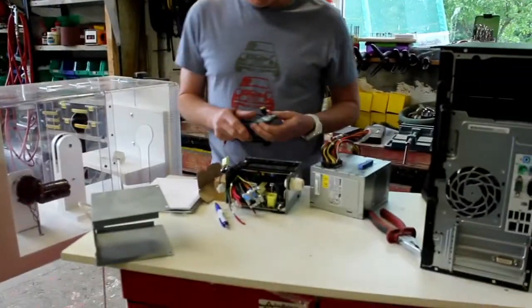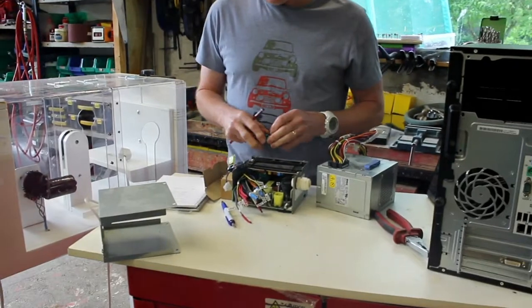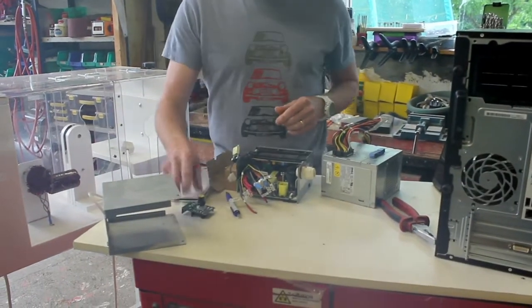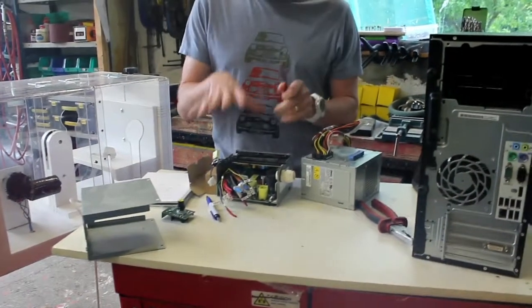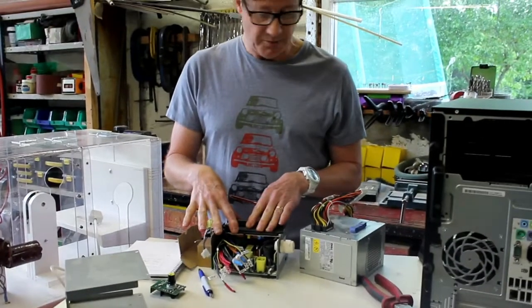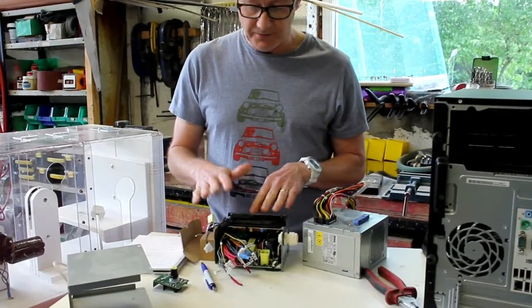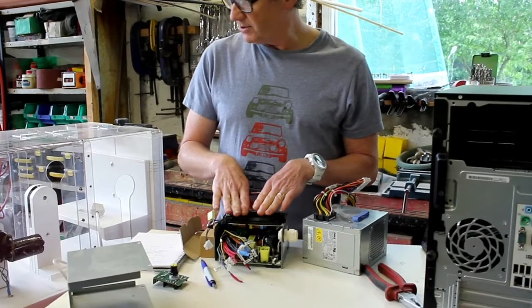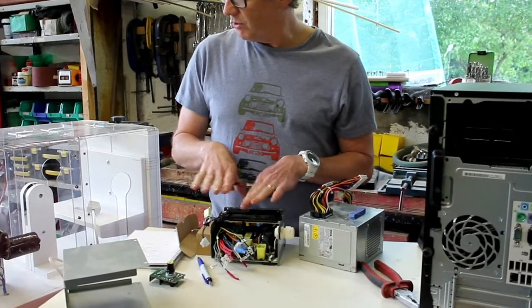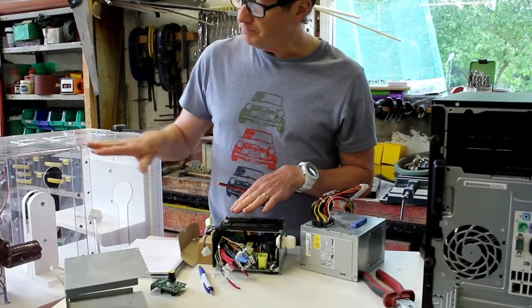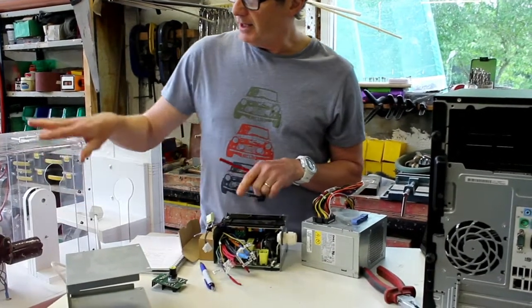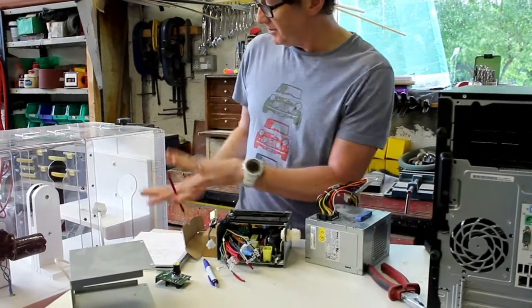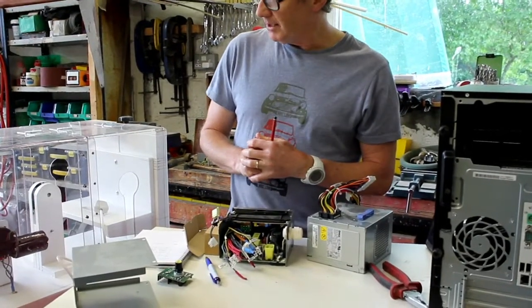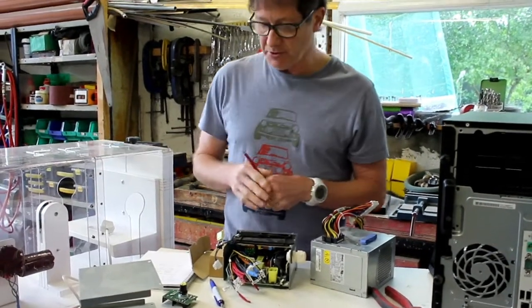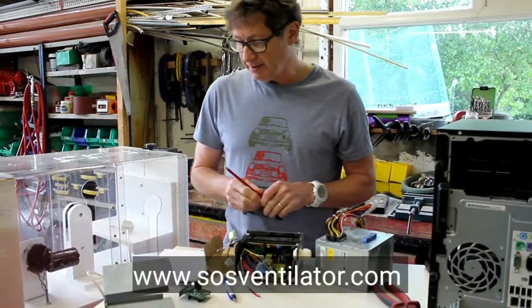So that's really about it. Everything worked well for us when we tested it and ran it. There were no major problems. The circuitry for this has been put up on the website. The design circuitry for how the wiring is done to control the motor, the speed control on the motor, and the charging of the battery, which is essentially all that's needed in relation to this particular ventilator, which we refer to as the SOS ventilator.